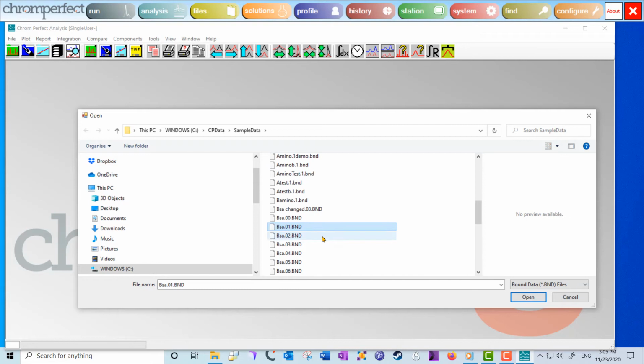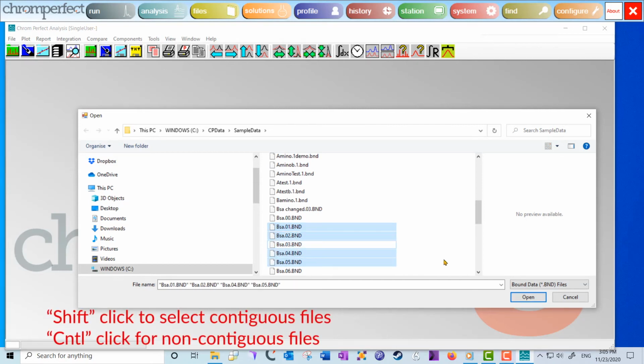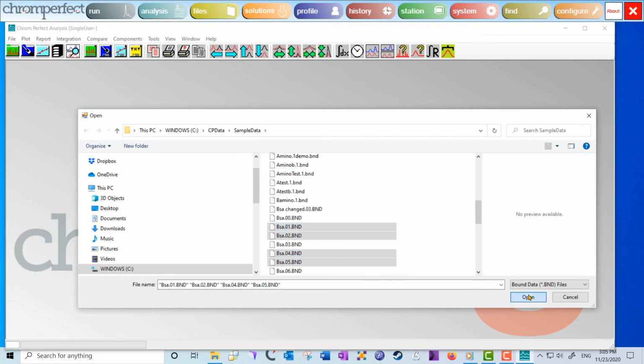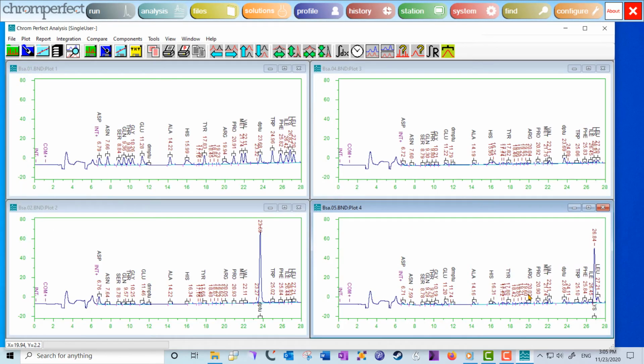Let's open some sample chromatograms with a known method and calibration file. Multiple files can be opened by using the standard Windows selection tools, Control-click or Shift-click. Plots within Analysis display not only the chromatogram trace, but also baselines, peak retention times, component names, and additional information according to the method file settings.